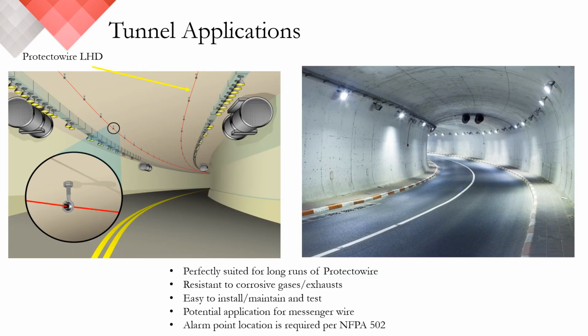Road tunnels are a great application for any of the linear heat technologies as well. Where the detector is positioned above the travel lanes, it is high enough out of the way that false alarms should not be a concern, and it's well suited for the extended runs typically seen in these areas. However, some of the tunnels we see internationally can be as long as 7 miles plus. In a facility this large, fiber optic likely presents the most effective and versatile tool available. As we discussed earlier, fiber optic is an active detection system reporting real-time temperature conditions throughout its length. The beauty of having this real-time information is invaluable when determining the location and direction of the fire.